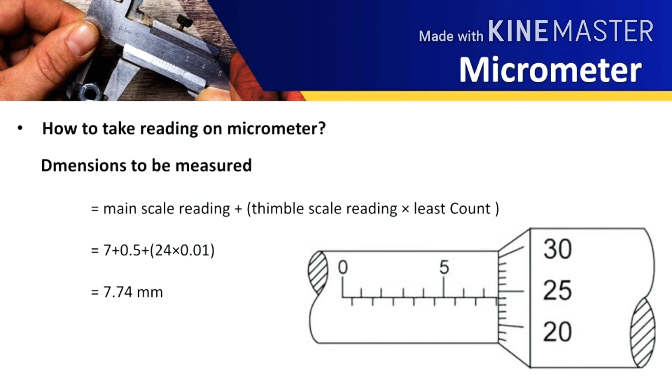So the dimension to be measured is equal to main scale reading plus thimble scale reading times least count. Put the values in the formula as we can see in this image. Main scale reading is 7.5 and the thimble scale reading is 24. And the least count we have calculated is 0.01. So the dimension to be measured is 7.74 mm.